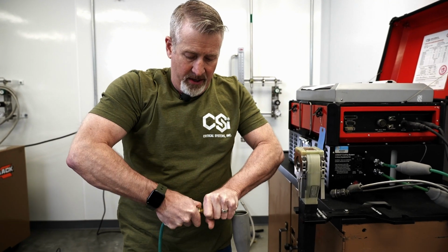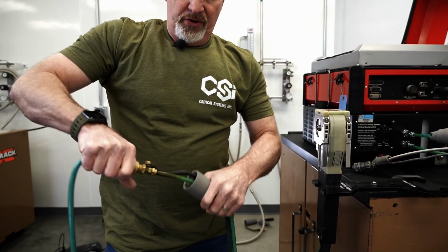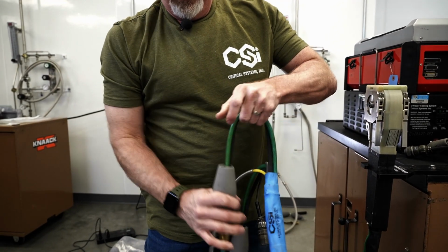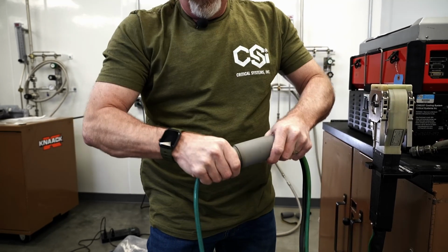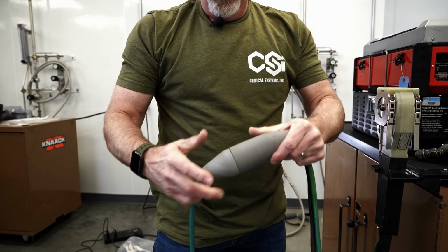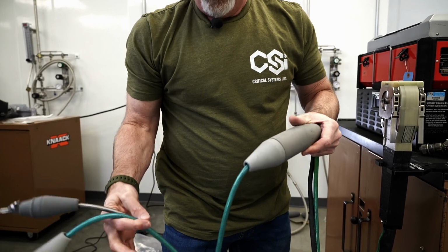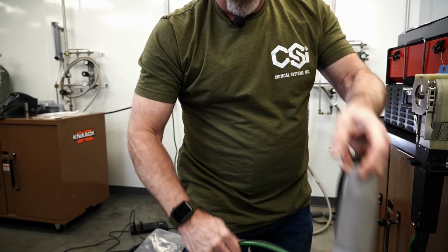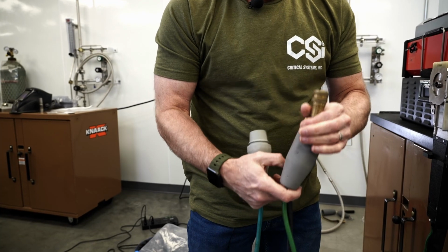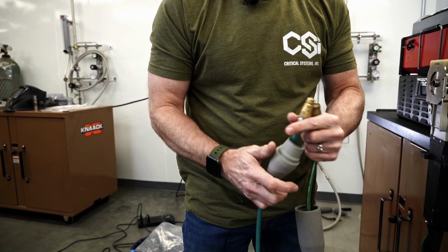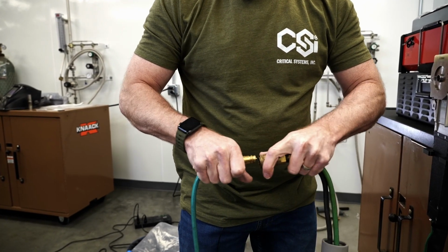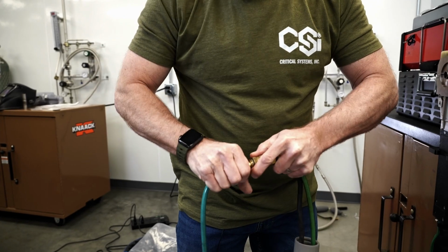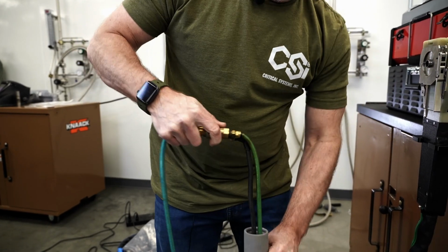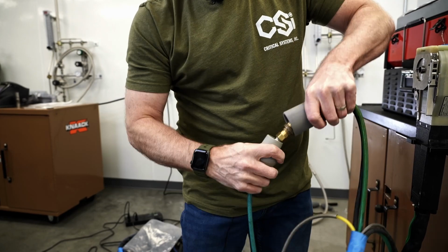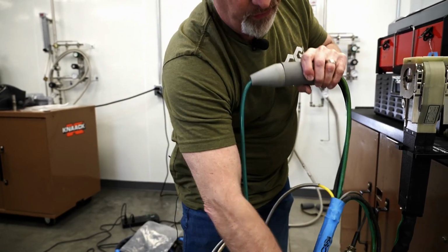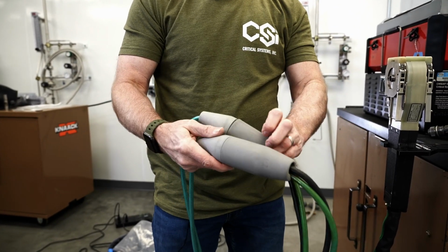You connect the brass fittings, you seat the boots snugly over them. They fit together like that. That is now safe to weld. That will not cross arc with this connector or any other metal that might get in between them. Again, it's important that you seat both boots so that they're both protected from each other.